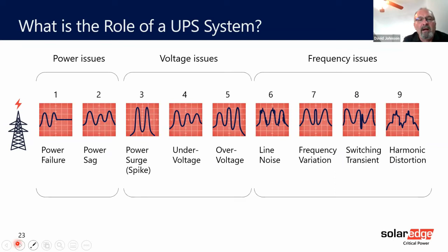So its two purposes are, number one, to avoid power failures. So it's uninterrupted. That's why it's called an uninterrupted power system. But the second function is to provide 100% power conditioning 100% of the time. So that's the role of the UPS. If we take a little closer look at it, the actual UPS in the bottom corner here, there are four components: the rectifier, the battery, and the inverter, and then there's typically a static switch bypass that wraps around.